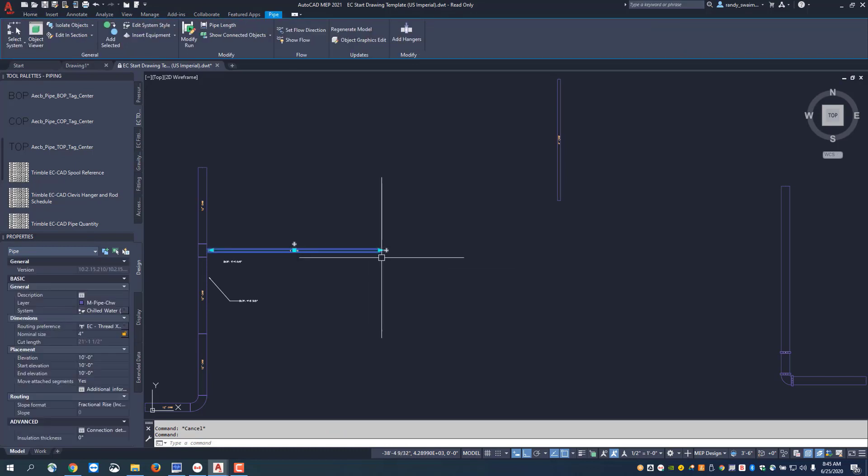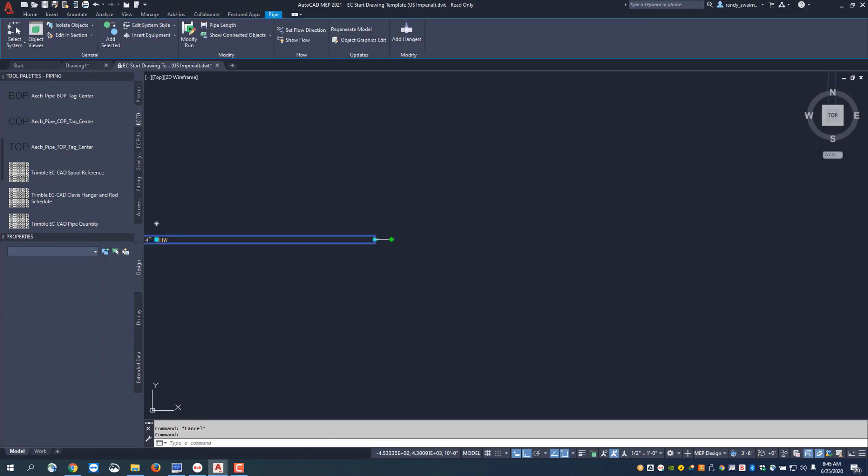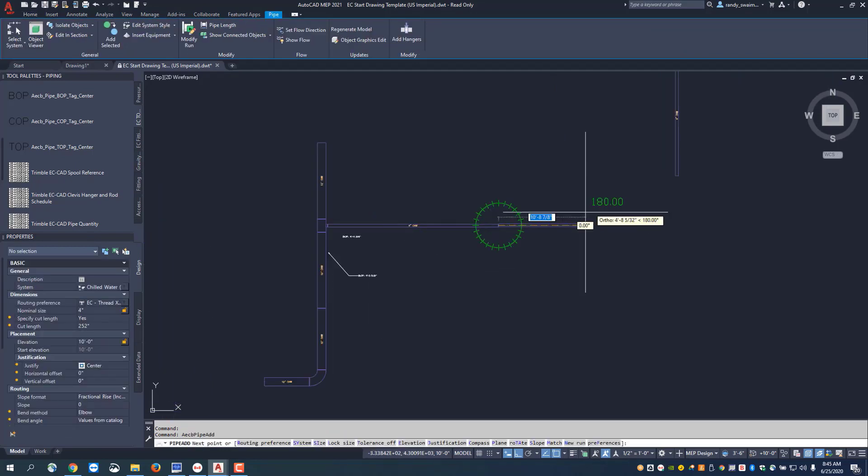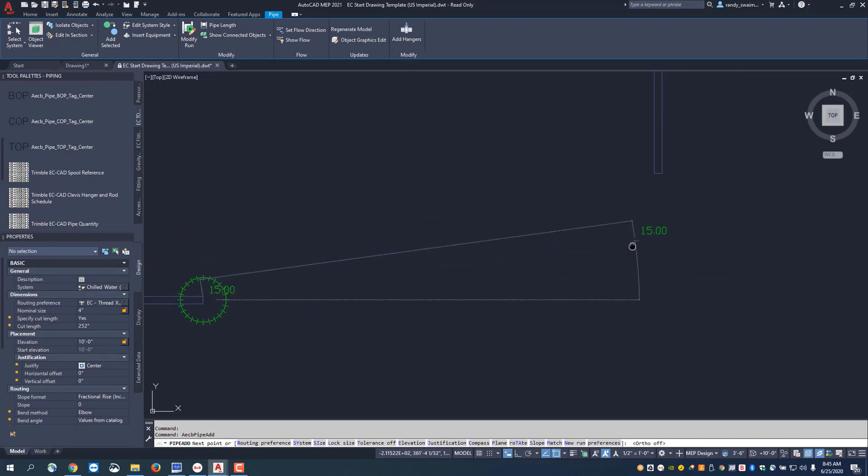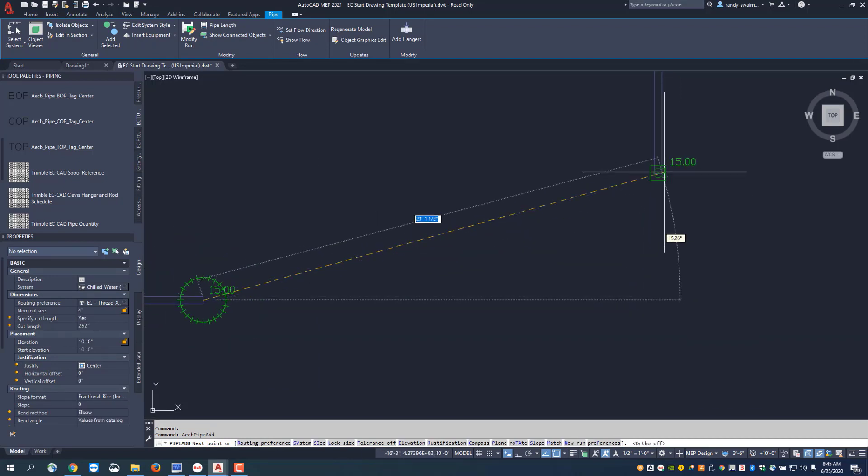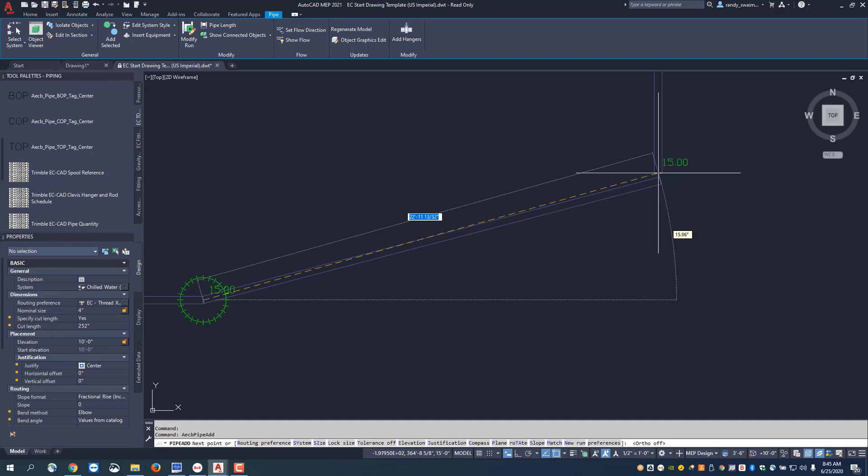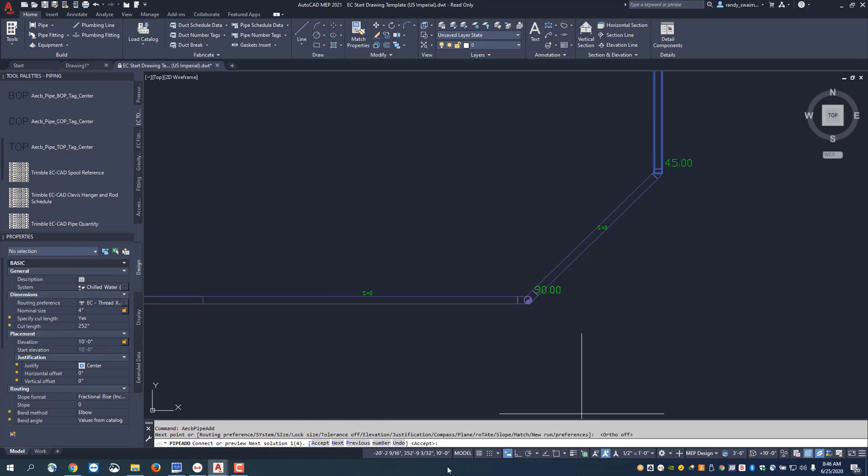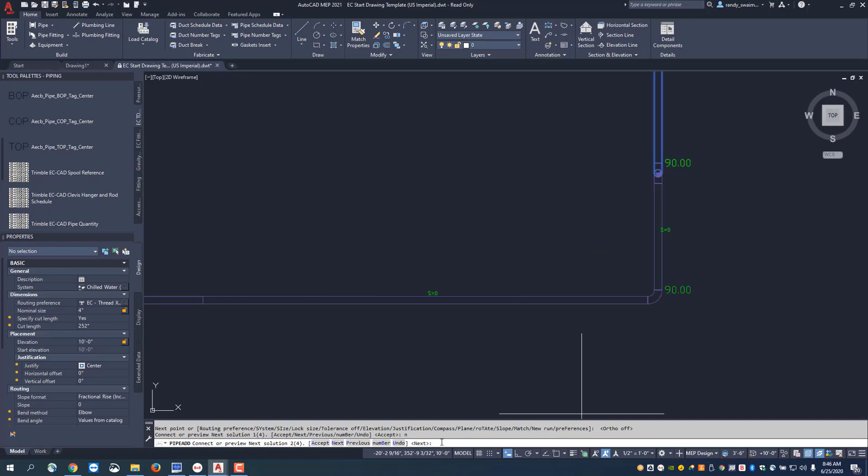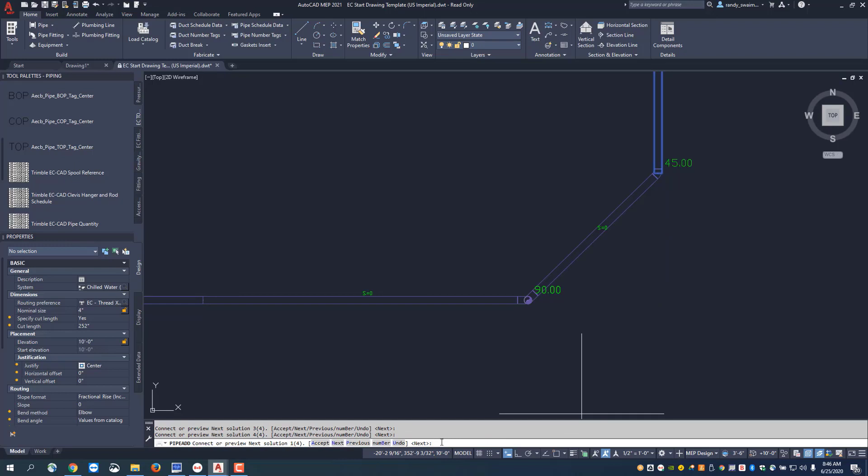I'm going to click on this run, grab the intelligent grip, and get my snap onto my other piece. When I get close enough you'll see the snap light up. Then I can click that. It's going to tell me on the command line that it's found four different ways to connect those two objects. If I type N on the command line and hit enter, that takes me through the different scenarios based on the fittings I have loaded. When you find the scenario you like, you just hit A for accept and it draws that in.